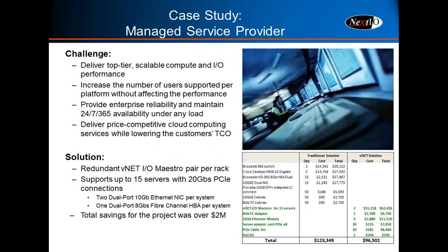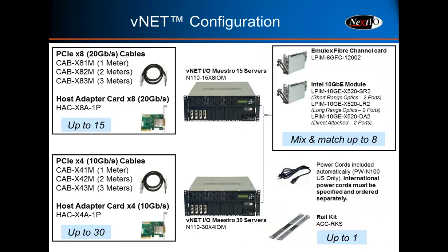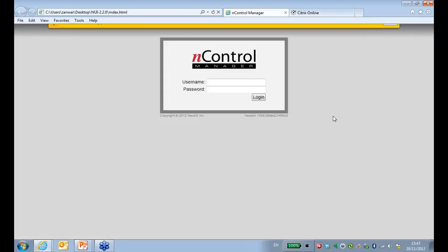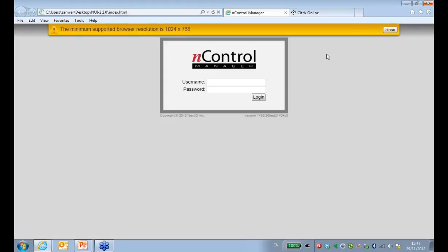This slide is a hosting provider example. We do show some cost savings here, but to be honest with them, it was the cables that were a problem. Their cables weren't under the floor — they were carried on a catenary at the back of each row of racks, and they had a health and safety issue. Cables are copper — they're metal. If you have a bunch of these, especially in a large rack, they can be quite heavy. So they had a health and safety issue with the number of cables leaving the rack. I'm going to jump to the GUI now and spend about five minutes on this.